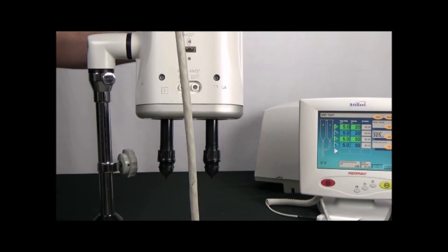The reason we're doing this is because there's an O-ring inside the injector head designed to act as a barrier to keep any spilled fluid out of the head. However, this O-ring may have a small amount of dried contrast or saline built up on it, which can cause squeaking or even rattling of the piston during movement.